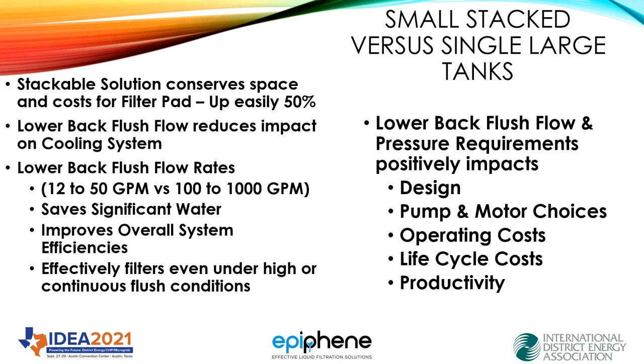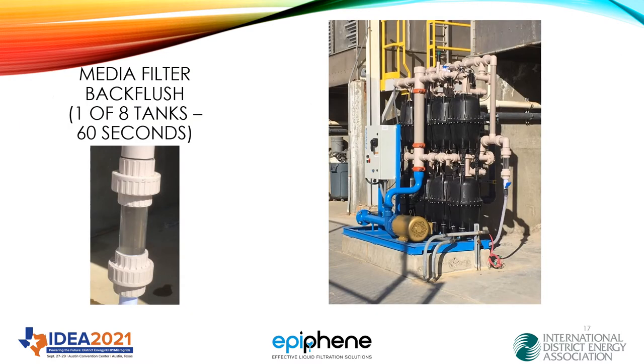So let's look at a recent application where we provided eight 12-inch tanks, 200 gallons a minute on a six-foot by three-foot pad. They wanted 20 micron filtration. The beauty of this is not only did it take out the silt, but it was also able to back flush with about 12 to 13 gallons a minute in 60 seconds. Typically a 200-gallon filter would run 200 gallons for the back flush and maybe three to five minutes — so this is a dramatic improvement.